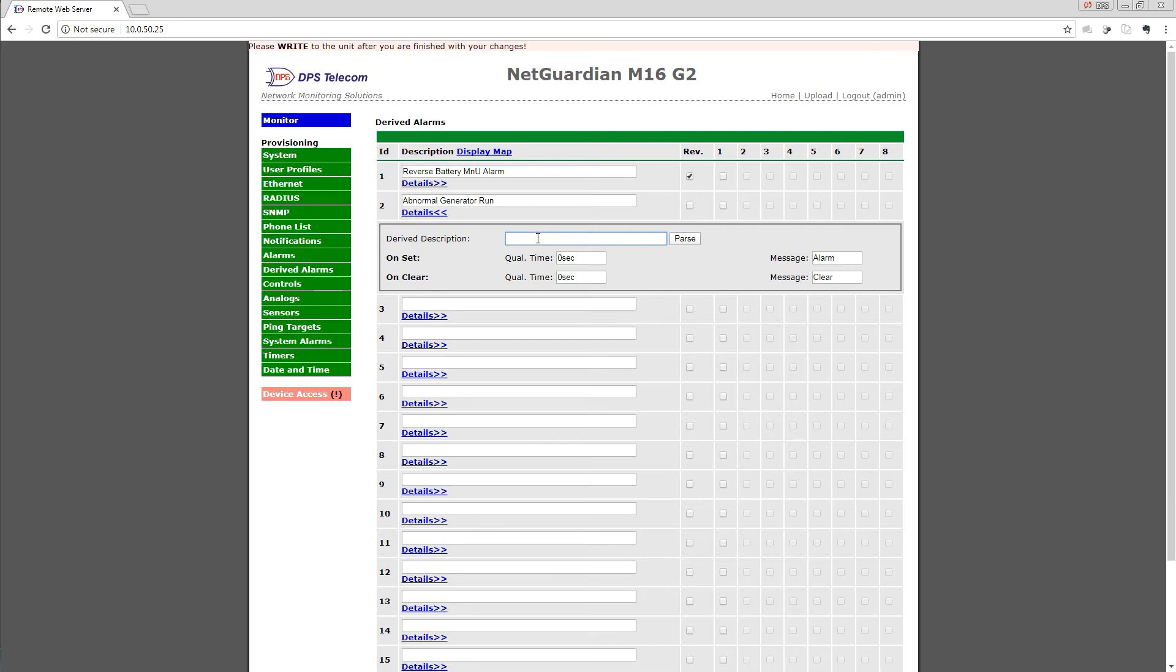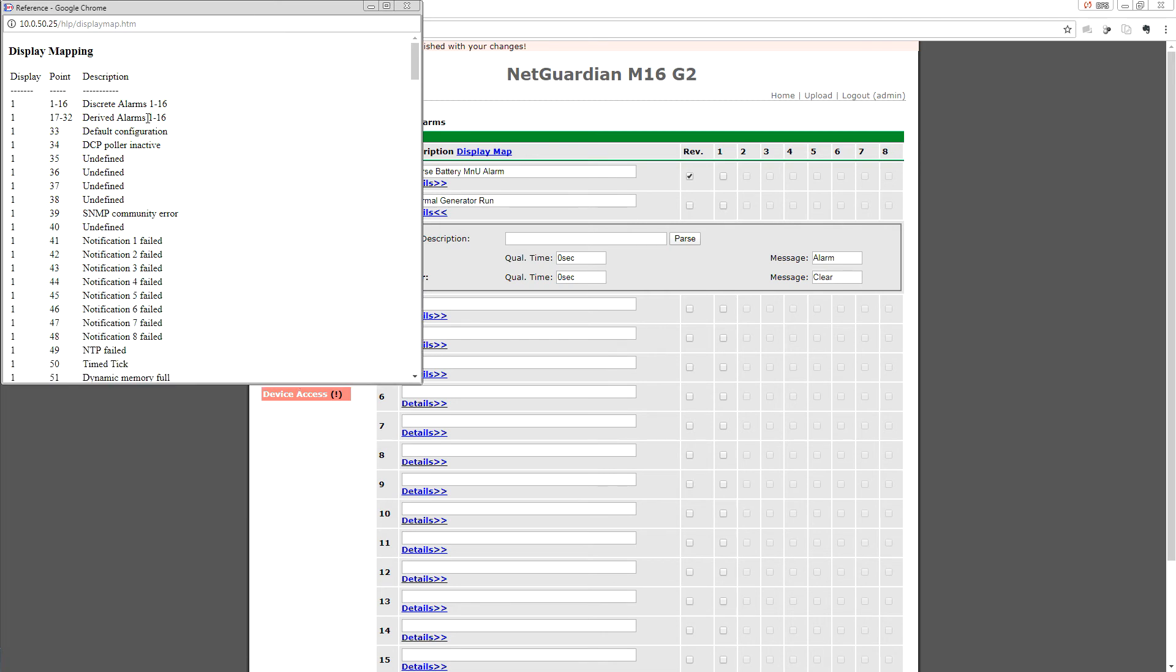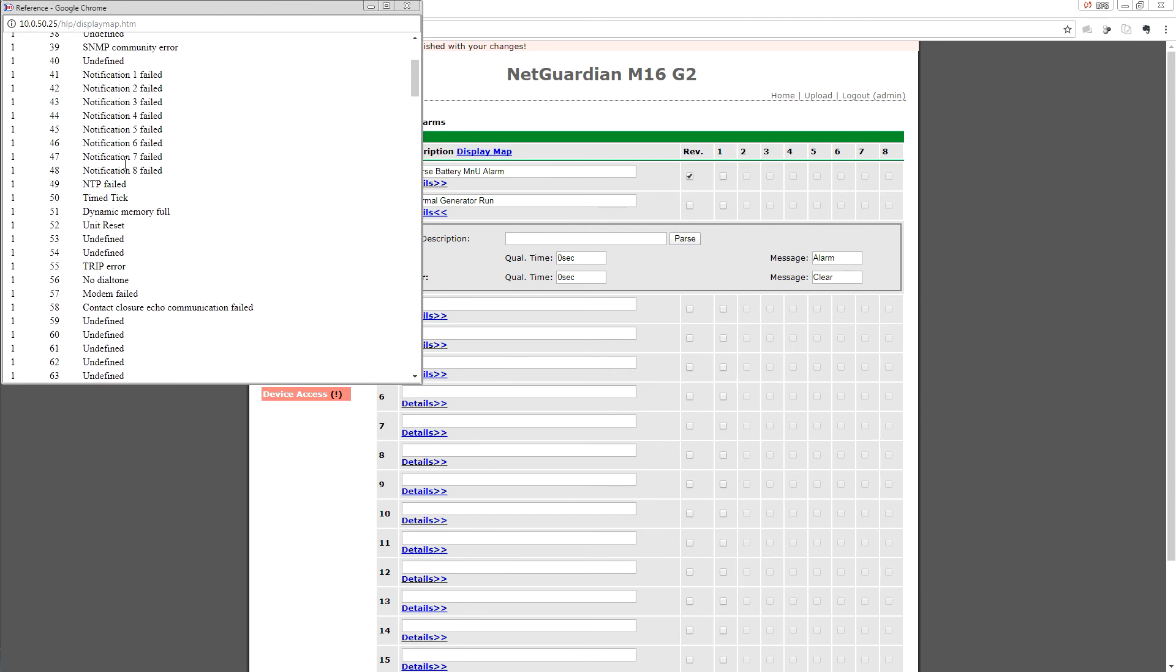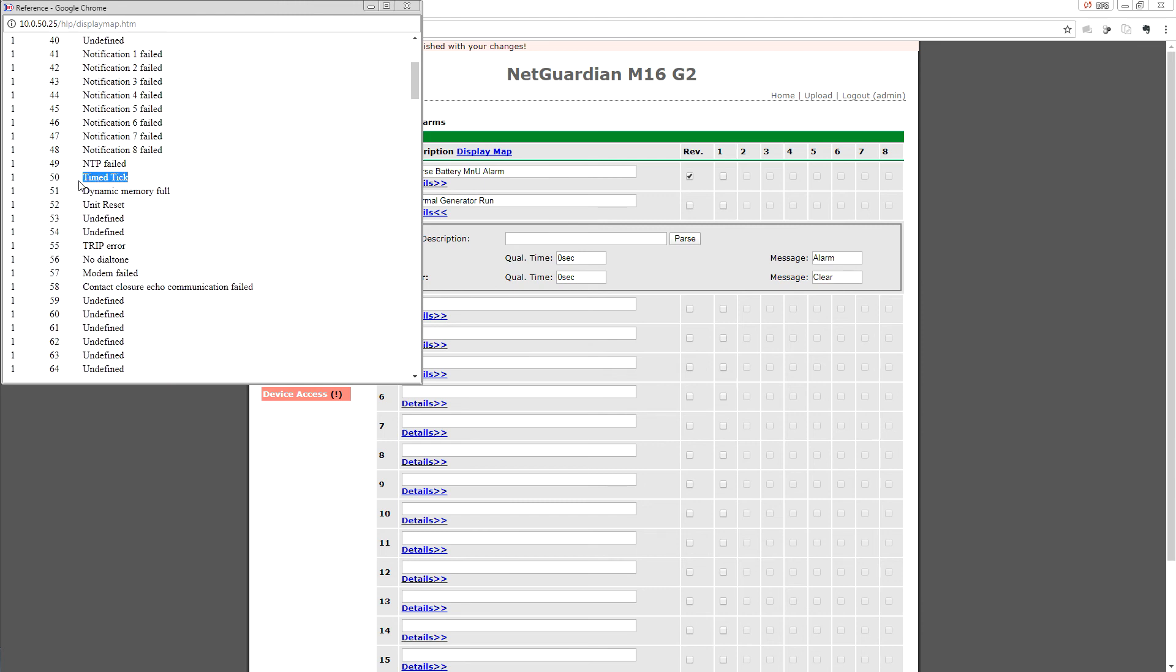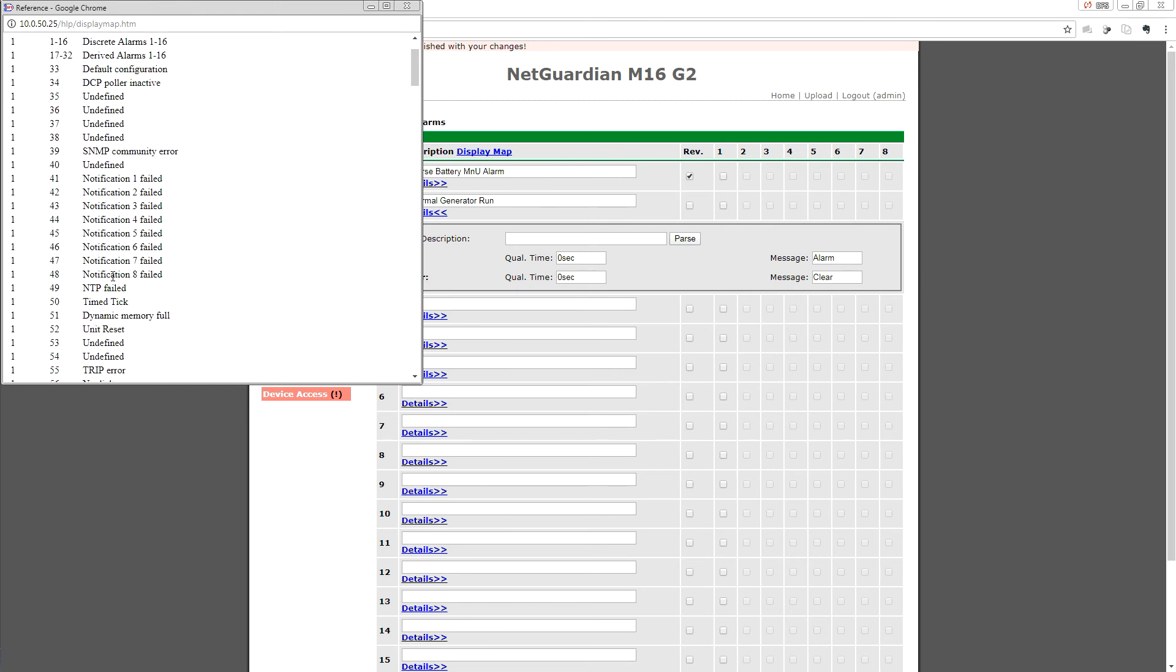To work that out and incorporate our two components, we need to go to the Display Map. As you recall, we set up generator run on discrete alarm point 4, so you can see in the display map that on the first line, discrete alarm points 1 to 16 are point 1 to 16 on display 1. So our generator run is display 1 and then point 4 inside of this range, so display 1.4 is generator run. The other piece was our time tick, which is down here, display 1.50. Generator run is display 1.4, time tick is display 1.50, and that's going to be set during our weekly generator exercise window.